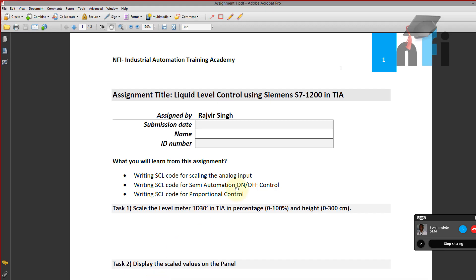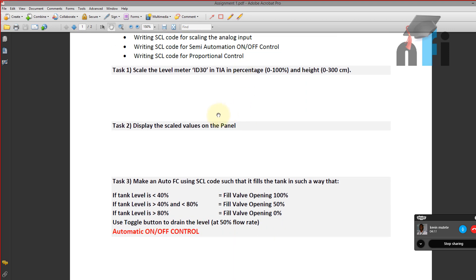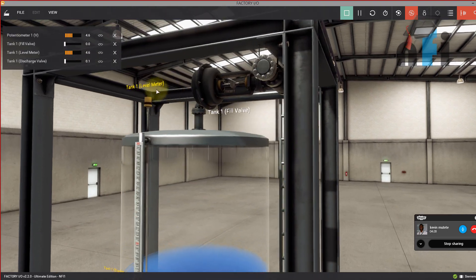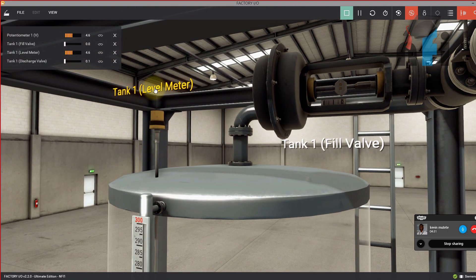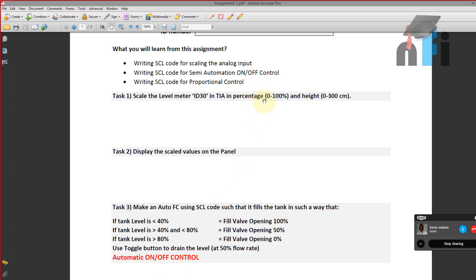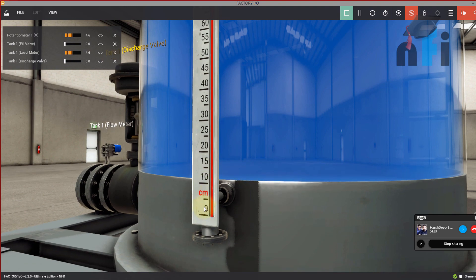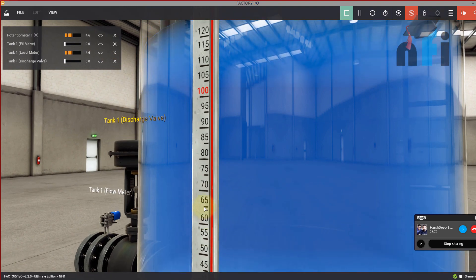The first objective of today is to scale the level meter ID 30 in TIA portal in percentage. Right now the value from the level meter ranges from 0 to 10, and at maximum level it will be 10 and minimum it will be 0. We have to scale this value from 0 to 10 to 0 to 100%, and also scale the height from 0 to 300 centimeters.